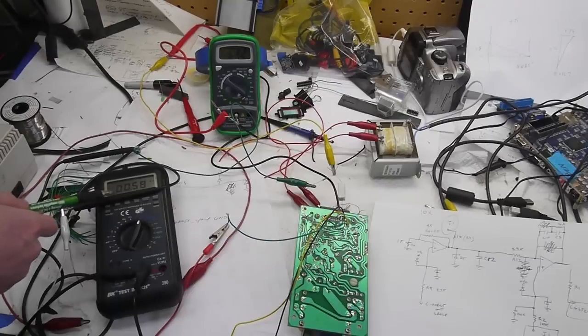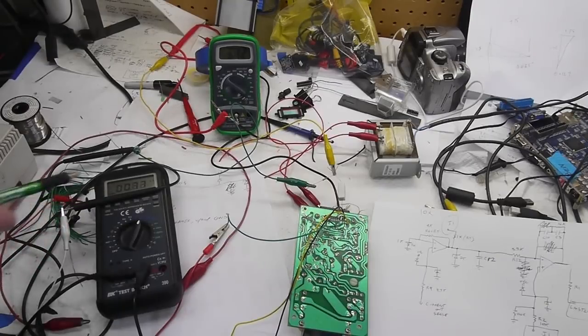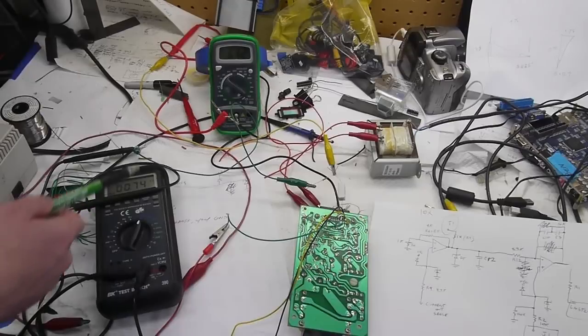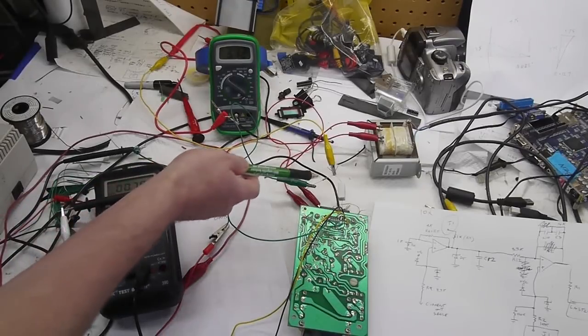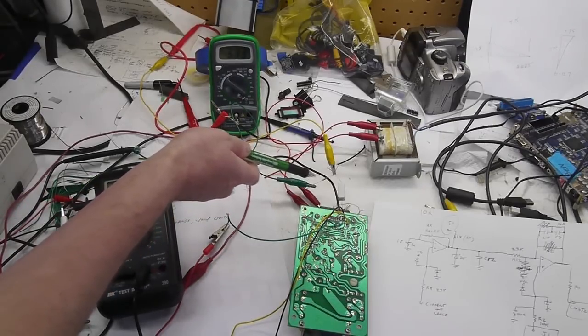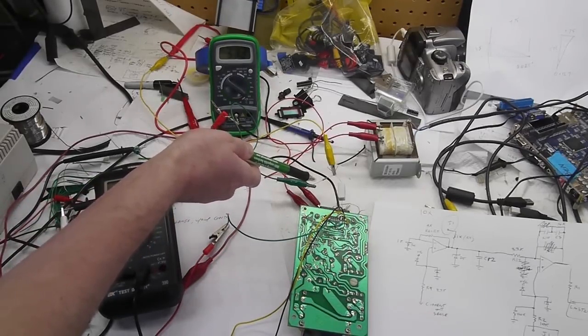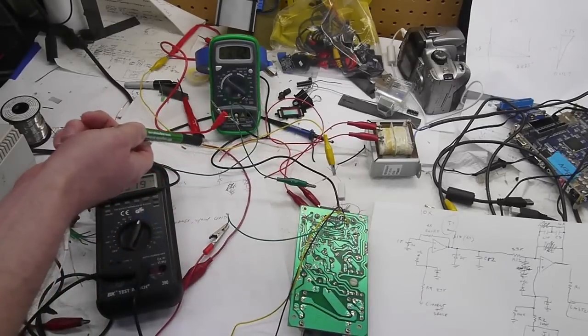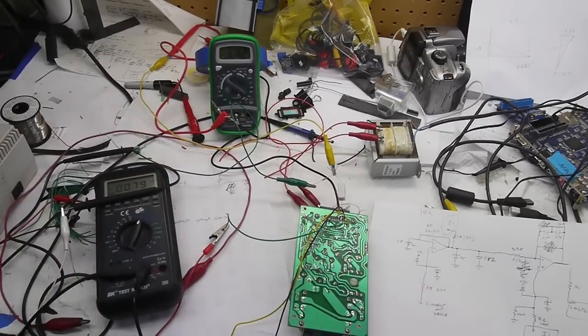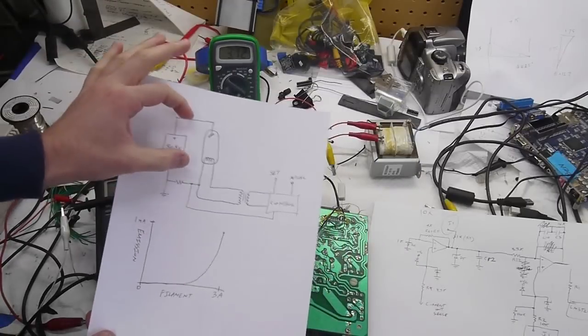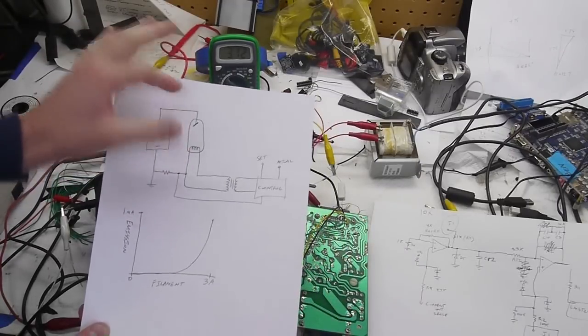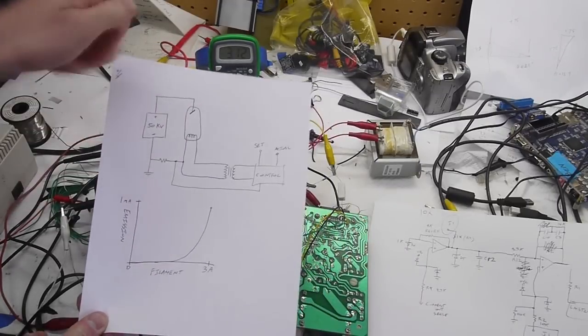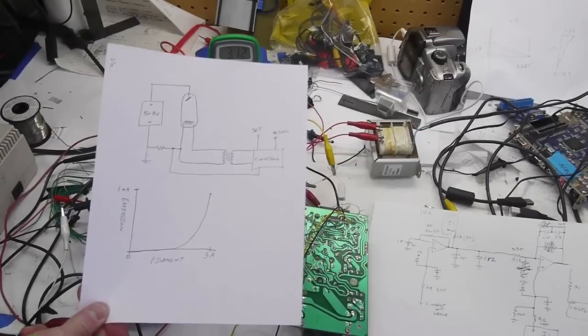And I can adjust that with a supply here. So I've basically just connected my power supply through this, I think it's about a 5K resistor here, into the filament loop. So I've basically put a power supply in place of the x-ray tube with the resistor so that I can control the current going through there.